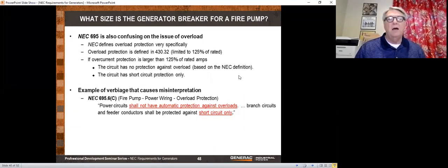But that is not the case with a generator, because you'd have to have a gigantic generator. So the generator generally just needs to be sized to be able to run that motor. It does not need to be sized for the locked rotor amps. We generally want the circuit breaker and the generator to be over 125% of the motor rating.